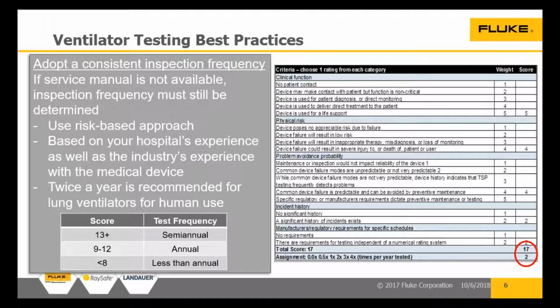So this one's going to be twice per year, and it will agree with most manufacturers. Although if you have a real high use inventory of ventilators in your hospital, you might get to a use hour much quicker than that. You might end up with 4 inspections per year, depending on how things are going. So that's those, and the use and abuse, which goes here in the problem avoidance criteria, are why the University of Vermont looks at this about every 2 years throughout their full inventory. They just spend a little time running down through, it doesn't take very long, and just comparing that back to the manufacturer and figuring that out.